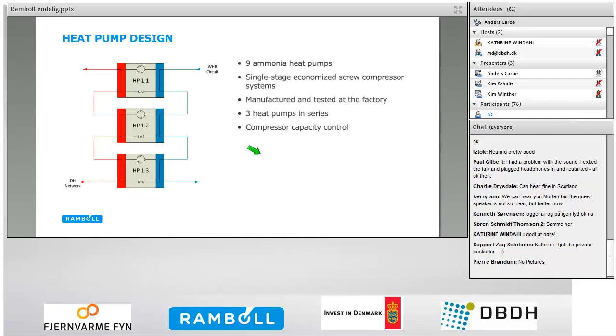The heat pump units have been supplied by Johnson Controls and were manufactured and performance tested at their factory before being delivered to site for final inspection, final installation and commissioning. On each heat pump group, the water on the waste heat recovery circuit is chilled in 3 stages, and it's also heated in 3 stages on the condenser district heating side. This 3-step principle reduces the lift between the cold and the hot side, which then improves the efficiency of the heat pump system. The compressors can regulate their capacity, which will ensure that the chilled water supplied to Facebook has the correct temperature.